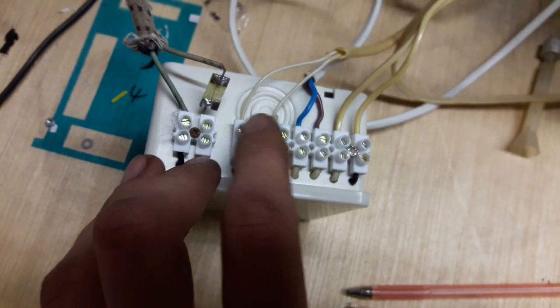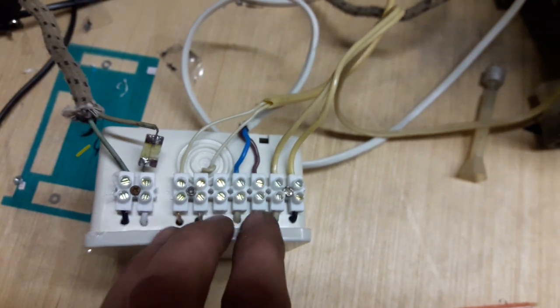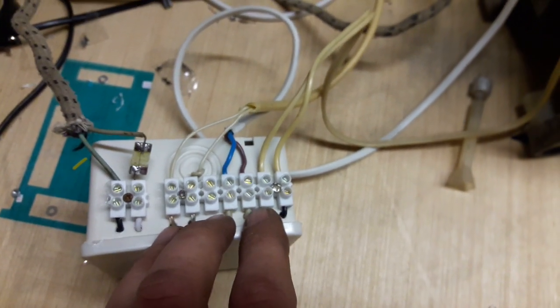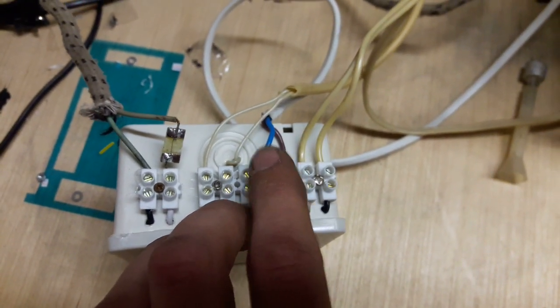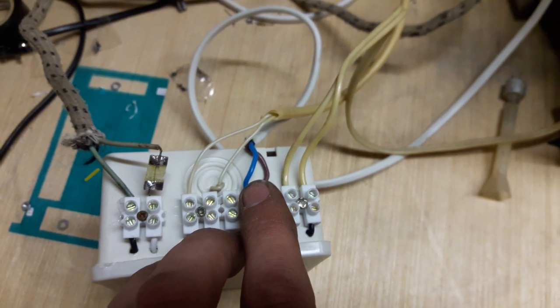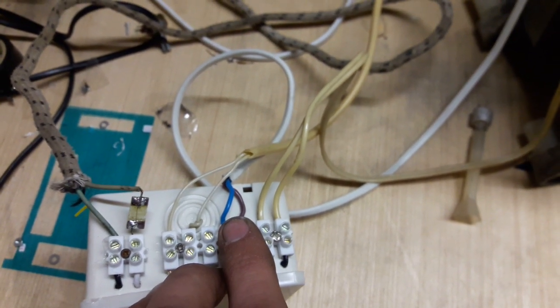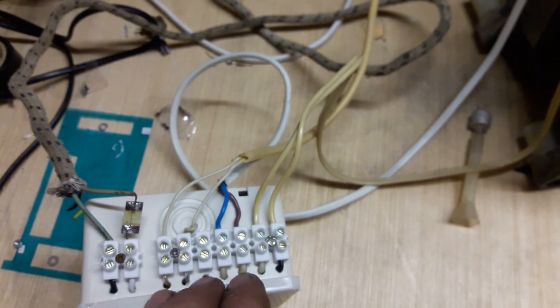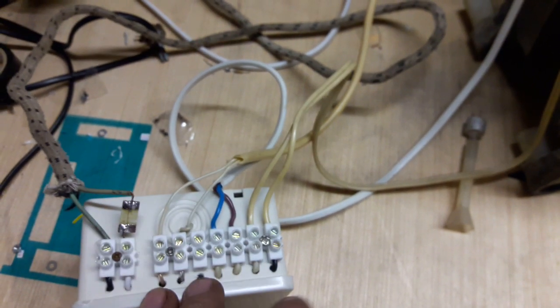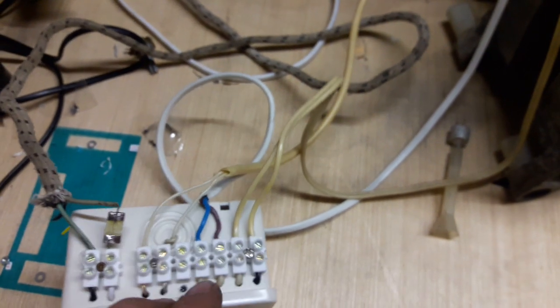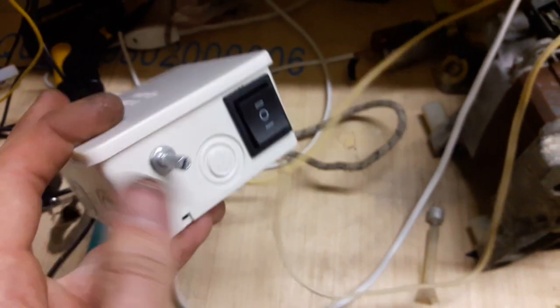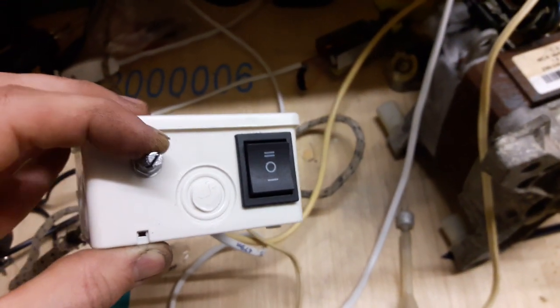These two wires on the left, the thin wires are the tacho. It's a little generator. These ones are either the field coils or the rotor windings. It doesn't really matter. All that matters one winding here, another winding here. And then with the help of the switch you can commutate them to run the motor either forward or reverse.